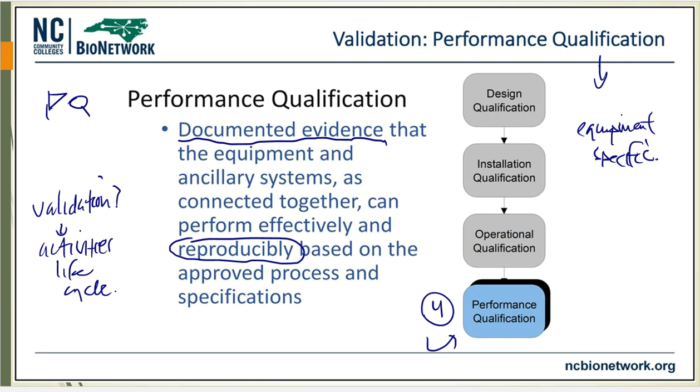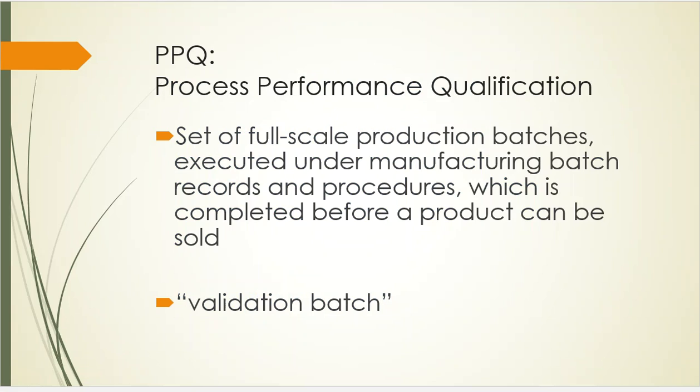Because if I don't do the IQ, OQ, PQ before that installer takes off and out of here, and I'll never see them again, what's going to happen if I try to use that piece of equipment, like that centrifuge, and it just fails, or it's not doing what it's supposed to be doing? That is a problem, and that can stall the entire production line or the laboratory testing line if we are not very careful.